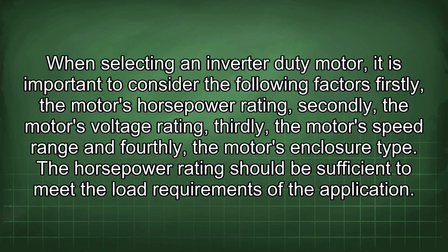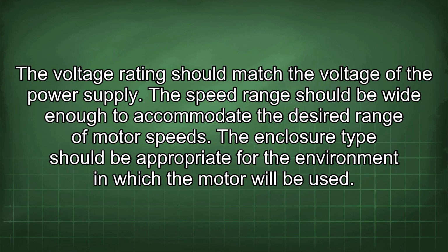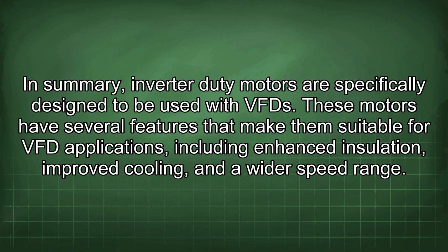The horsepower rating should be sufficient to meet the load requirements of the application. The voltage rating should match the voltage of the power supply. The speed range should be wide enough to accommodate the desired range of motor speeds. The enclosure type should be appropriate for the environment in which the motor will be used. In summary, inverter duty motors are specifically designed to be used with VFD.